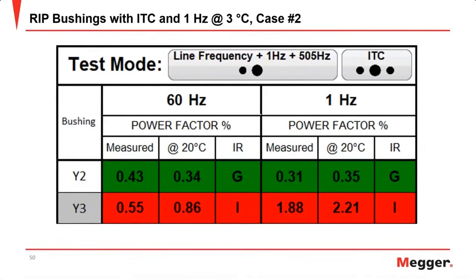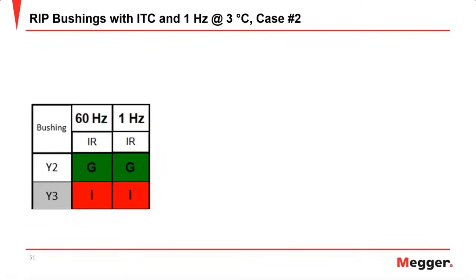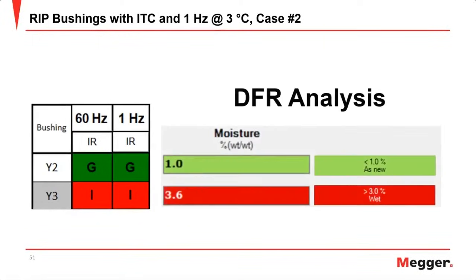And then finally, this customer wanted to take this testing 1 step further. And this brings us back to the dielectric frequency response, where if you were going to implement DFR into your test routine, one of the best ways to do that to really maximize your team's productivity is to perform 60 Hertz testing along with 1 Hertz testing, since it's the same machine, same connection, software already configured to do those additional tests. And then when you think that you have an issue, say where the 1 Hertz is higher than expected, then you could bring out the full dielectric frequency response instrument and confirm your analysis.